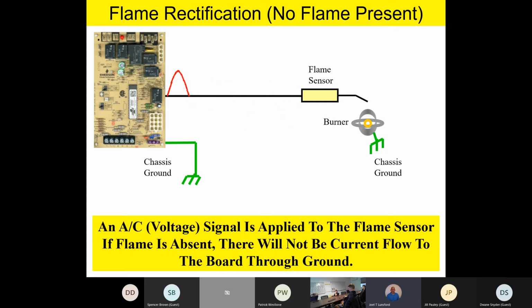It's not going to pop that 3 amp fuse. It's not going to pop the main fuse or the breaker on the furnace, because it's an extremely high resistance circuit, although there's 120 volts on that flame sensor. So if you were to take your voltmeter and check that flame sensor to ground or neutral, based on the quality of your voltmeter, you're going to read anywhere between 90 and 120 volts on that flame sensor. So the flame sensor has AC voltage going to it all the time. Anytime there's power on the furnace, you're going to have AC voltage on that flame sensor, but there's no current flow. At this point, nothing happens. It's just an open circuit.